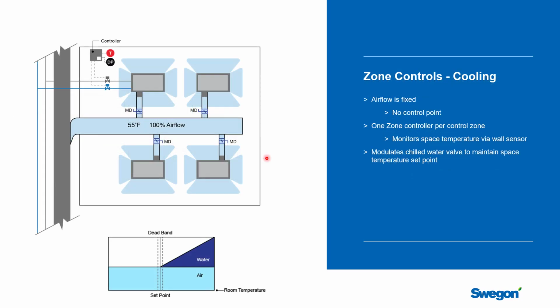So we talked about the air handling system and the controls in the air handling system. Let's start to zero in on a control zone. And the first thing we want to talk about is we shouldn't think of each chilled beam as being a control unit onto its own. You can mount unit controllers right on the chilled beam. You can have valves added right to the beam and treat one beam as a control zone, but it tends to be expensive. You can see that happening in, say, a private office where there's only one chilled beam in that space. That would make sense.